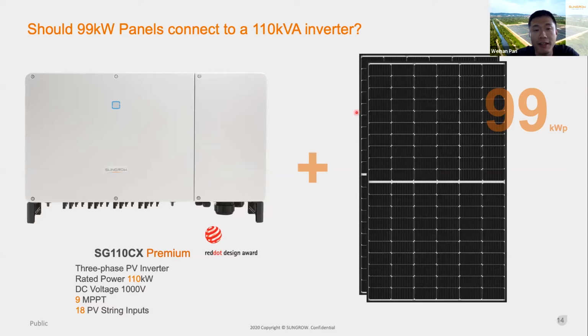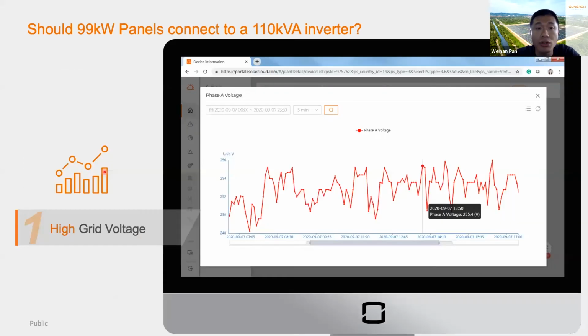And for this product, you might question why do we need to install a 110 kilowatt inverter for just a 99 kilowatt system for STC? Here I'm going to tell you why. Because on some occasions the grid voltage might be over voltage, too high. For example, in this iSolar platform, we could monitor the grid voltage.